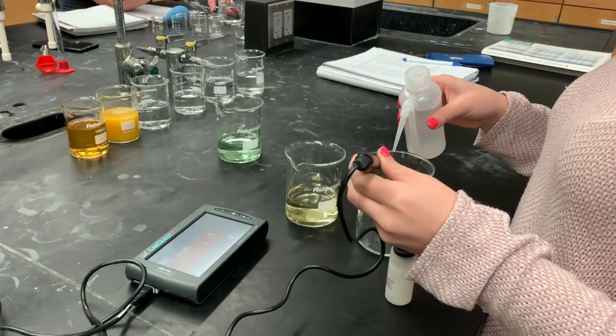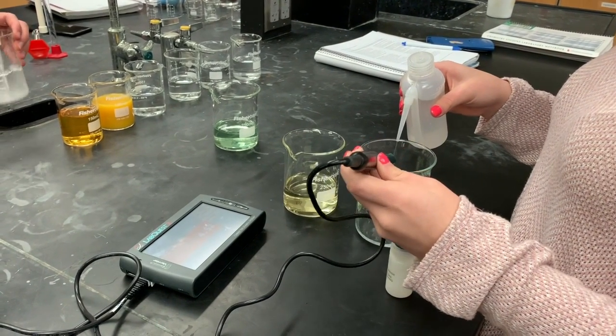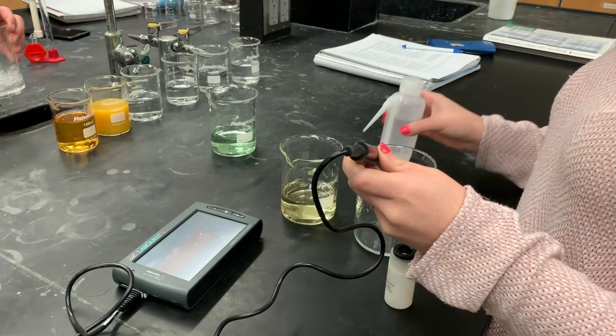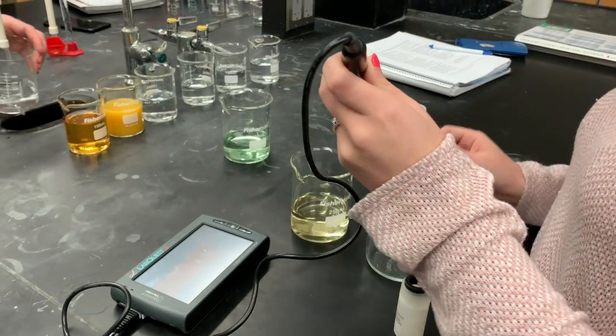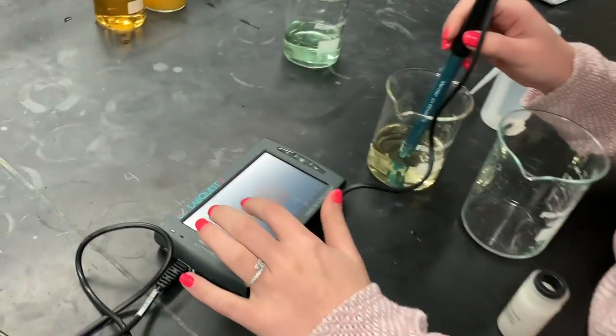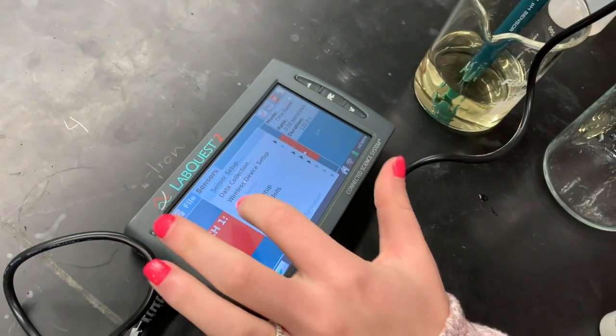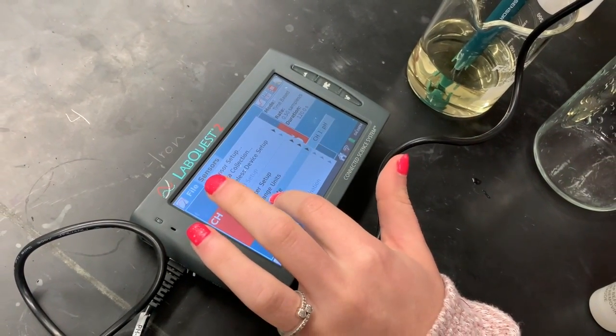To begin preparing the pH meter, the probe needs to be taken out of the storage solution and rinsed with water. It is important that the probe is kept in a solution at all times. Next, the pH meter needs to be calibrated. This is done by placing the probe into a buffer solution.